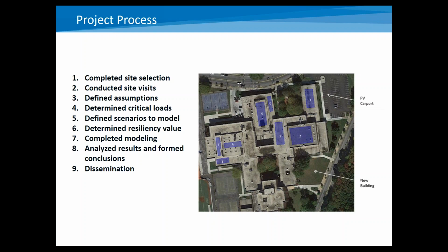Next, on number five, we defined the different scenarios that we were going to model. So we looked at different combinations of PV, storage, and backup diesel generation systems. And then we looked at designing these systems first purely for economic savings, and then second to sustain specified outage periods. And then we determined the resiliency value, as Lars described earlier, based on historical outages as well as the customer type and energy use of that particular building. And then we completed modeling.